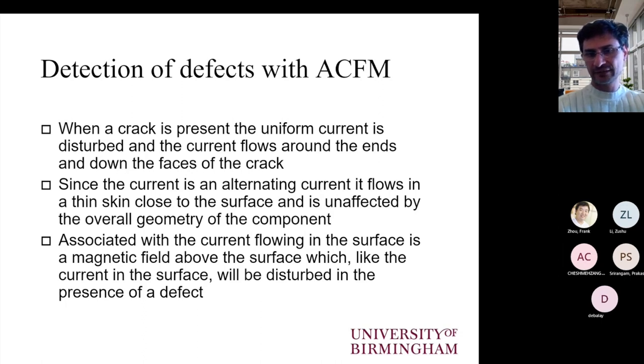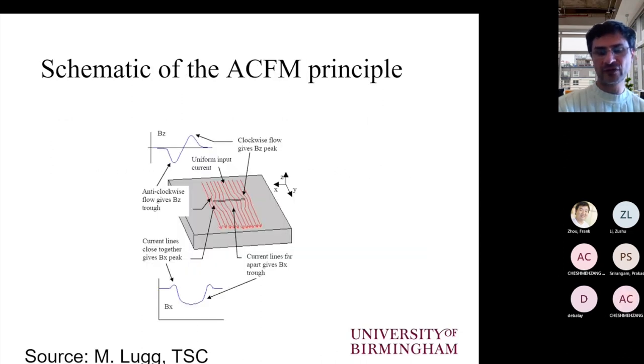So we have X, Z, and Y orientations that are of interest. And the Z orientation is the one that relates to the surface current lines that are flowing around the edge of the crack. And the BX is the one that is going below the crack, so it penetrates deeper in the material. This is the schematic diagram that shows the ACFM principle. So you can see here the corresponding BZ signal for the anti-clockwise flow and the clockwise flow around the crack edges, and the BX signal reduction for the current lines that are flowing at the bottom of the crack.